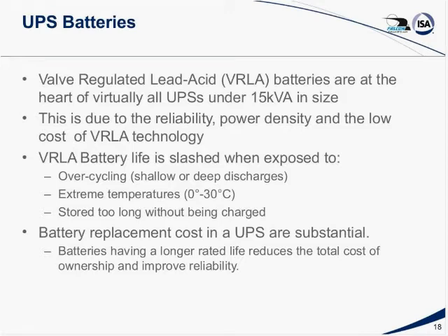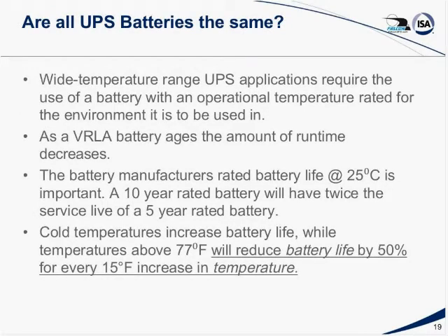Mike, are all batteries the same though for these UPSs? You know, all batteries aren't the same, even between what's called standard VRLA batteries. A high temperature UPS requires a battery that's rated for the higher temperatures especially. Lower temperatures don't affect the life of a lead-acid battery. In fact, they can improve the life of the lead-acid battery, but high temperatures can destroy the battery very quickly.